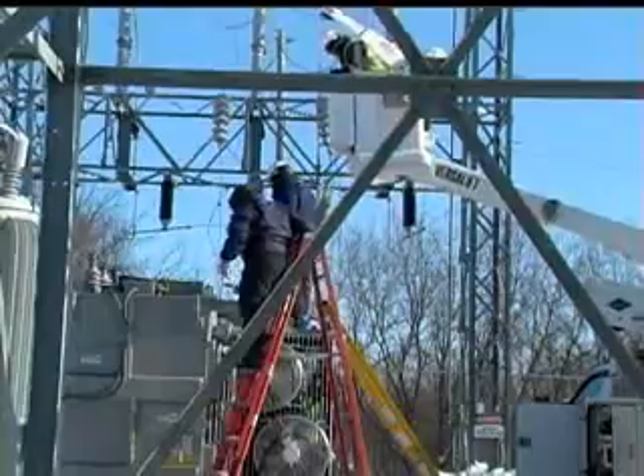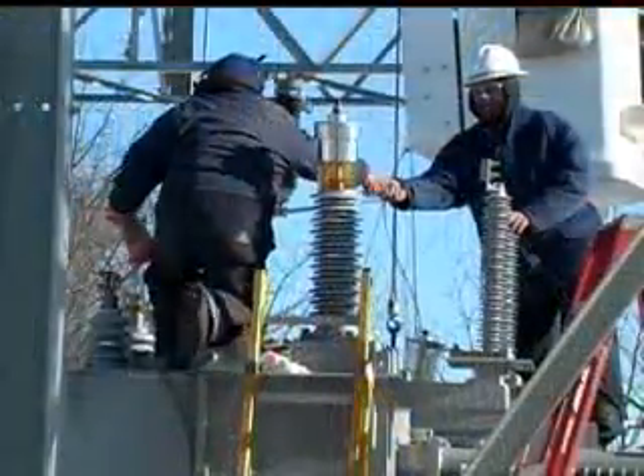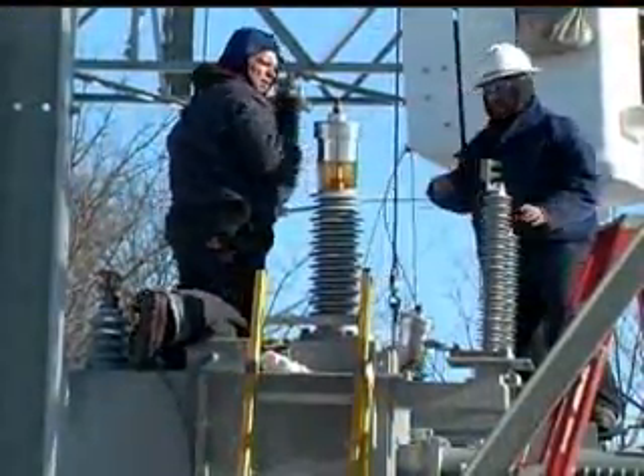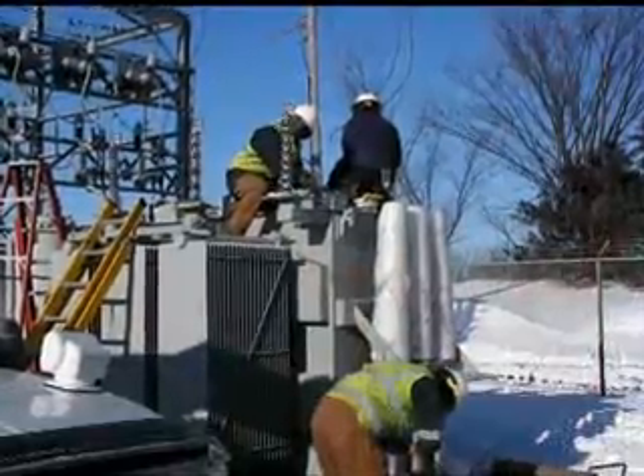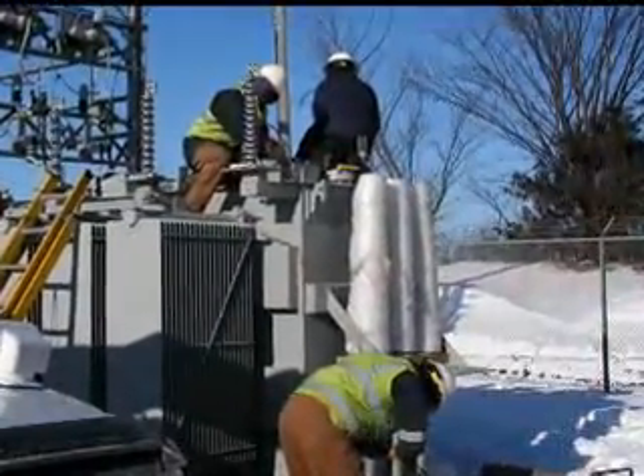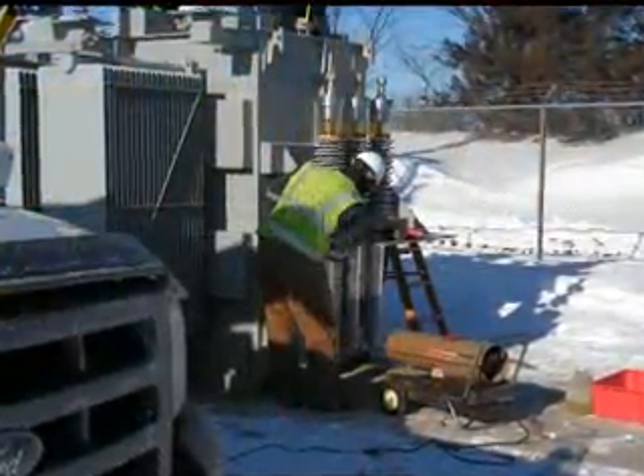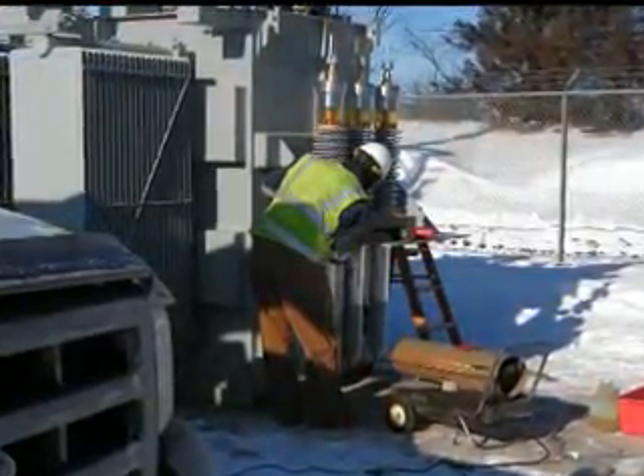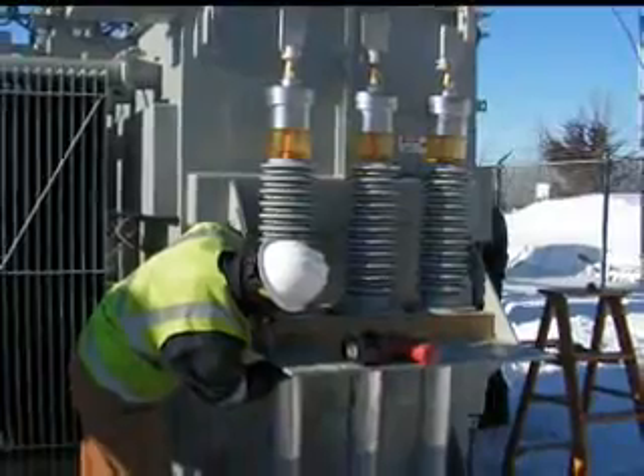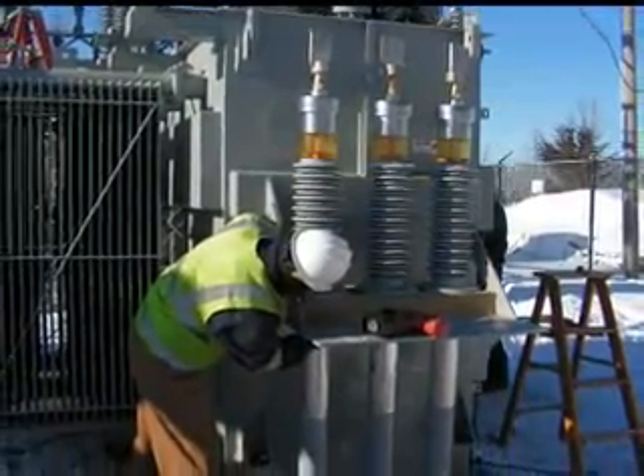The process of getting the new transformer operational starts with installing bushings and lightning arresters, which are shrink-wrapped and wired to the unit. Because of the cold temperatures, these bushings filled with oil needed cleaning. The ice was melted from them, and the road salt was wiped off with rubbing alcohol.